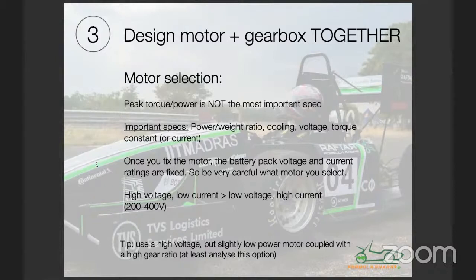Now, the downside generally of higher voltage, of course, is that you have to worry more about insulation and about your safety circuits. Electrical shock from a 48-volt system versus electrical shock of 250 volts is a very, very big difference. One will take you to the hospital. So when you're working with high voltages, you have to be extremely safe. You have to worry a lot about your safety circuits, your safety precautions, the way you design, the way you fabricate things. But on balance, given everything, a high voltage, low current system probably turns out to be better than a low voltage, high current system.